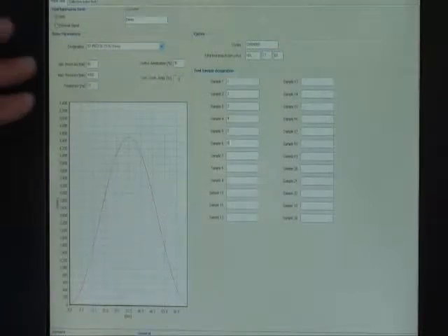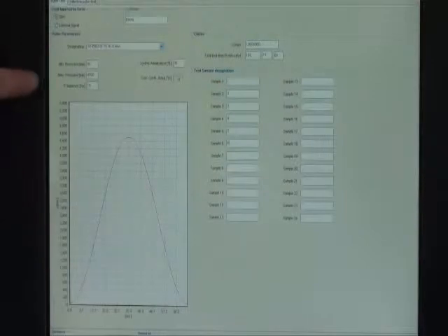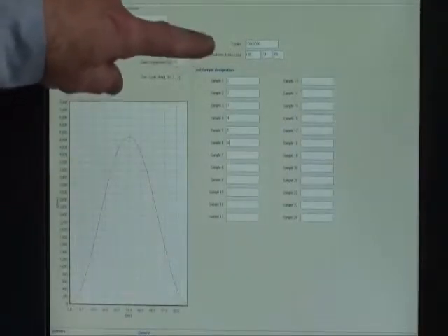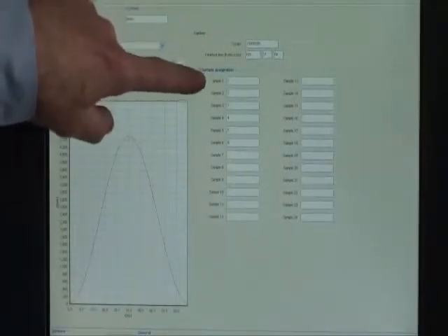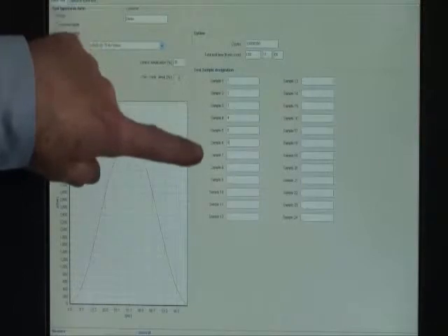Here on the setup screen, you can see that Brian has already input the test parameters, the high and low pressure set points, the frequency, the number of cycles, in this case 10 million cycles, and here we enter the sample ID numbers. We can go up to 24 samples on this test. From here, Brian will go into the test run screen.